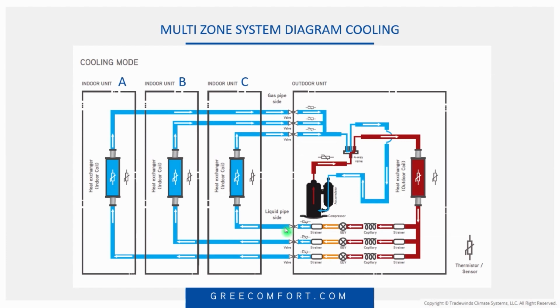I've also had calls where one of these thermistors was so far out of range, not enough that it actually showed electrically open or shorted, but the machine couldn't read that resistance properly. It never gave me an error code. All it did was make that circuit not come on. B and C work fine. A won't turn on, no matter what I do. Ohm out those thermistors, find one way out of range, change that thermistor, and now the machine works. So it could be something that simple.